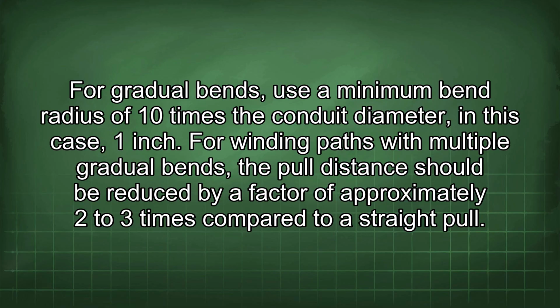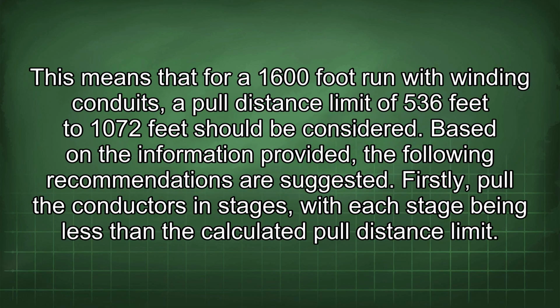For winding paths with multiple gradual bends, the pull distance should be reduced by a factor of approximately 2 to 3 times compared to a straight pull. This means that for a 1600-foot run with winding conduits, a pull distance limit of 536 feet to 1072 feet should be considered. Based on the information provided, the following recommendations are suggested.